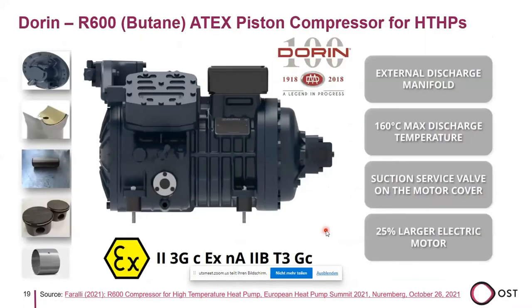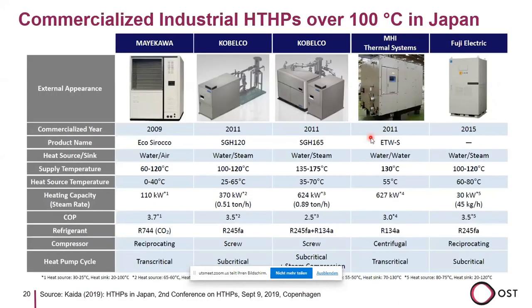There was also a presentation from company Dorin from Italy, which are compressor manufacturers, and they presented a compressor line for butane, which is a hydrocarbon, and it is very suitable for high temperature heat pump applications up to 160 degrees. So there are compressor manufacturers out there which develop new compressors to fit this high temperature heat pump market. In Japan, there are also products, and I would say Japan is a pioneering country in the topic of heat pumps.